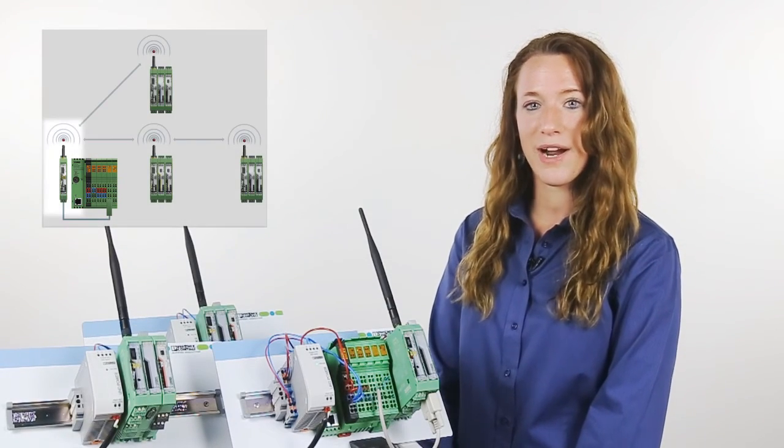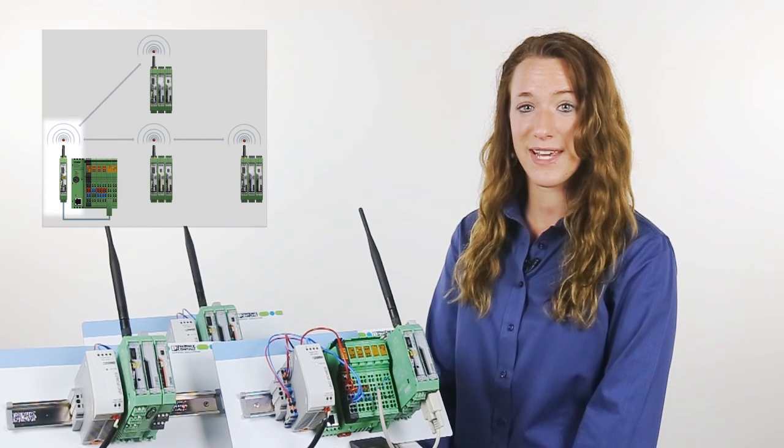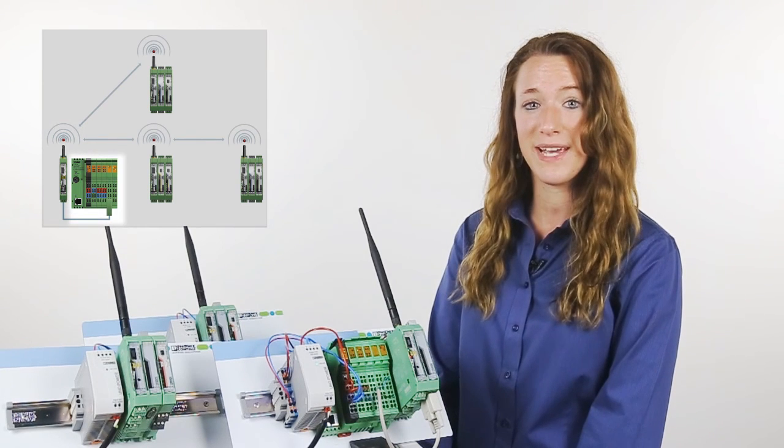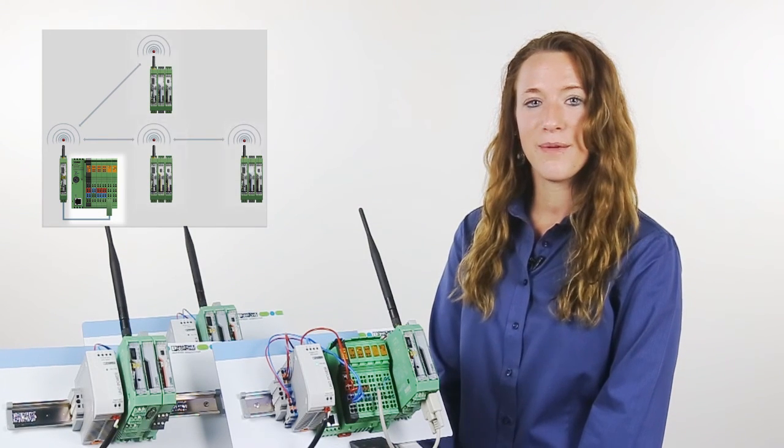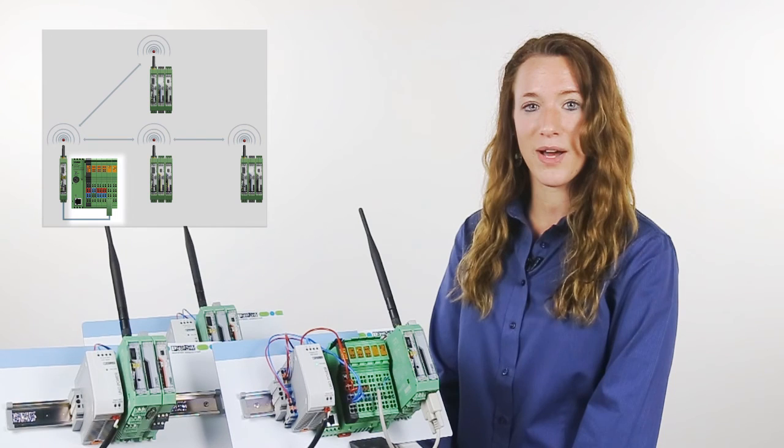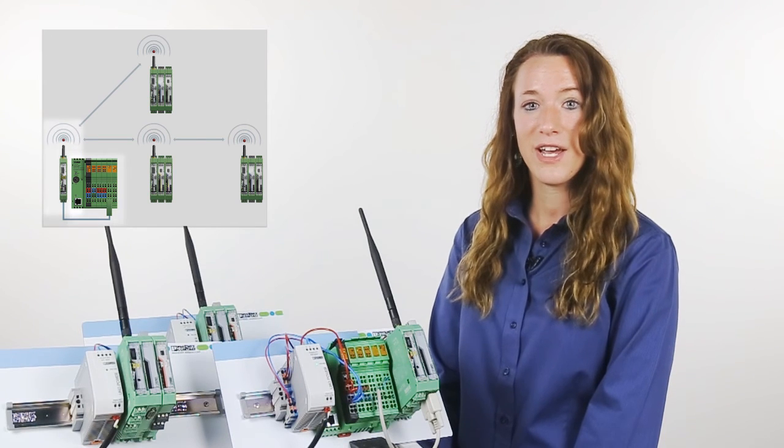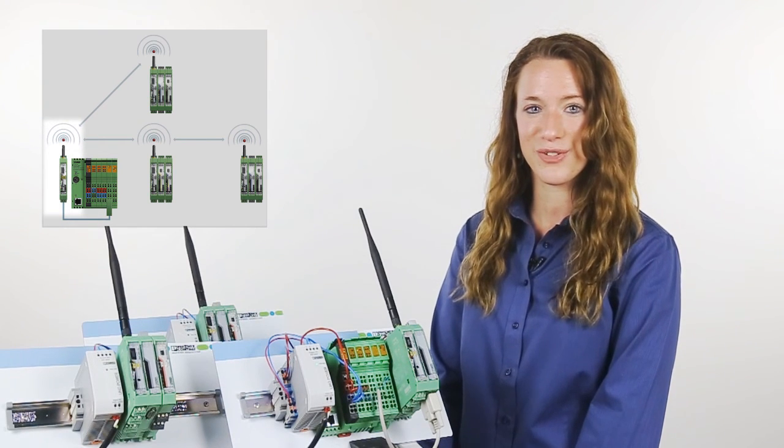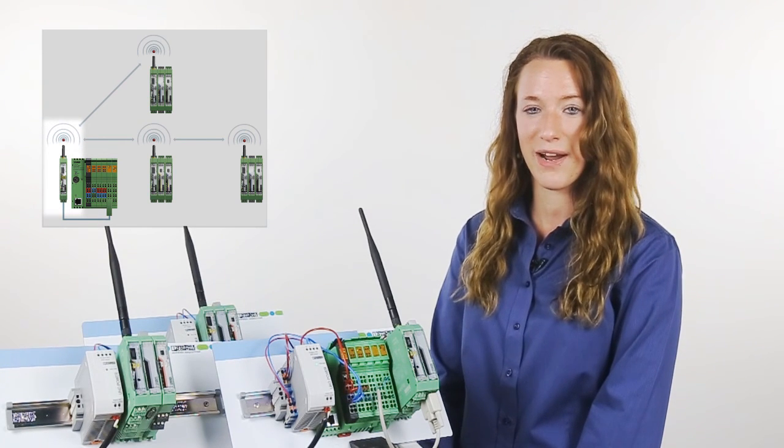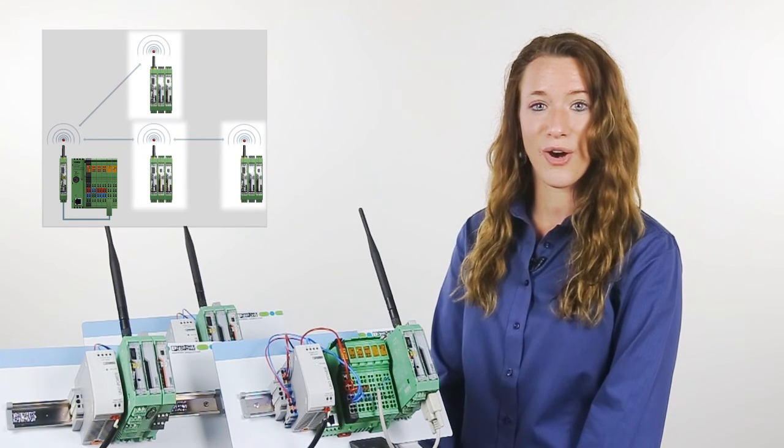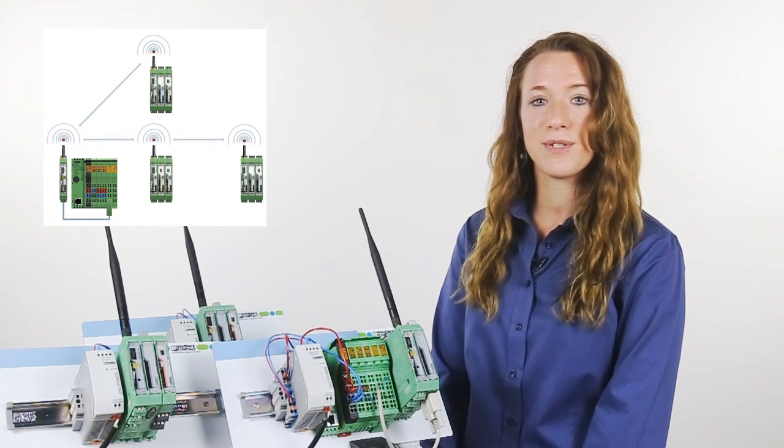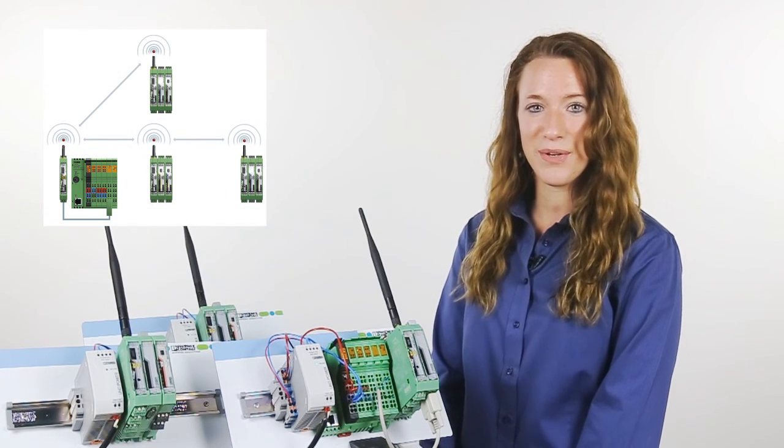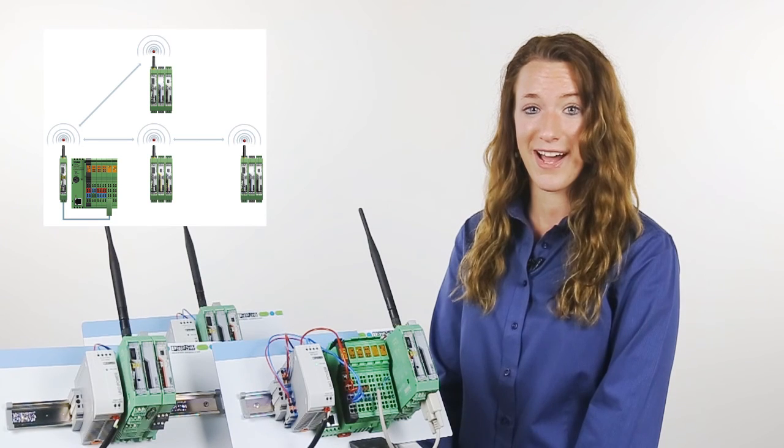The master wireless module is acting as a Modbus gateway between the PLC and the remote nodes. The PLC communicates to that single Modbus address configured in the master wireless module and the master wireless module then communicates to all the remote IO. This enables fast and easy communication between controller and remote IO.